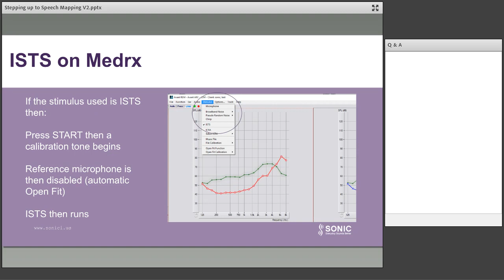Now, if you're using a Medrx on the ISTS signal, when you press start, what you will have noticed is that there's a calibration tone. It doesn't last for very long, and then when it stops, that's when the ISTS signal starts. In fact, there's an automatic open fit feature here. The minute that calibration is set, it turns off the reference microphone and uses that pre-stored calibration value. So you've already got an automatic open fit happening when you're using that ISTS signal.